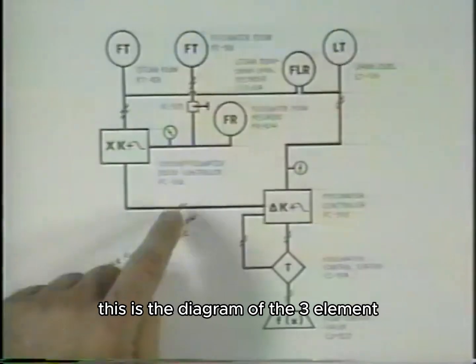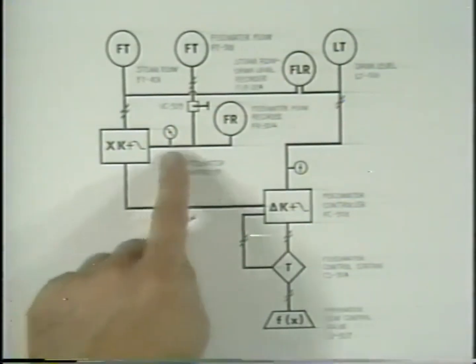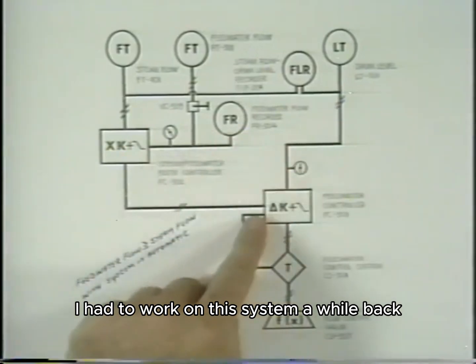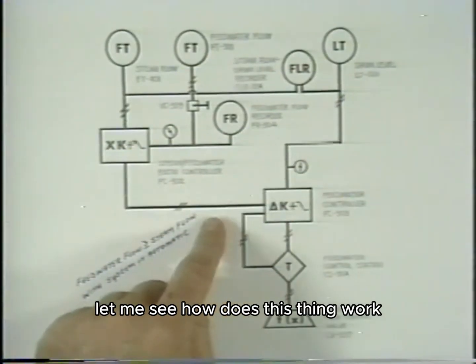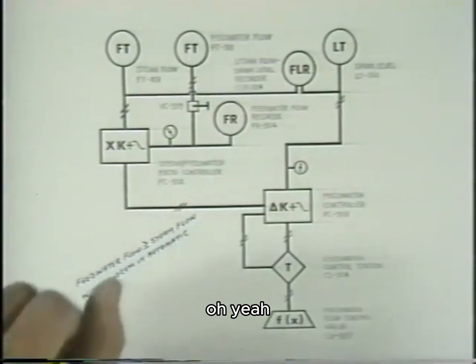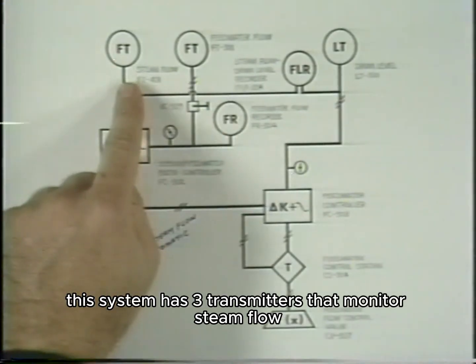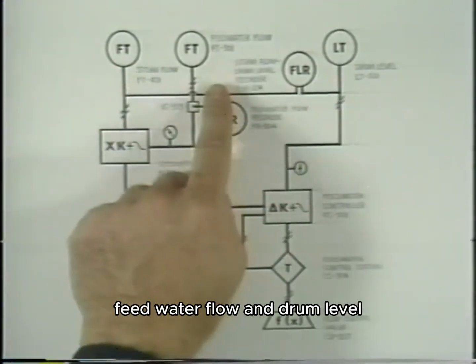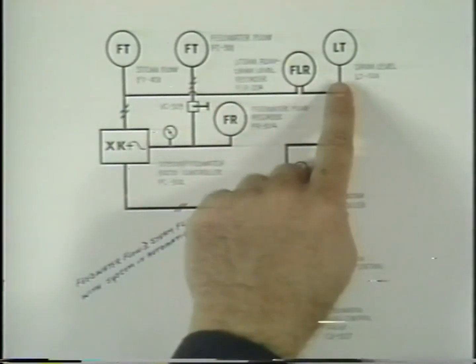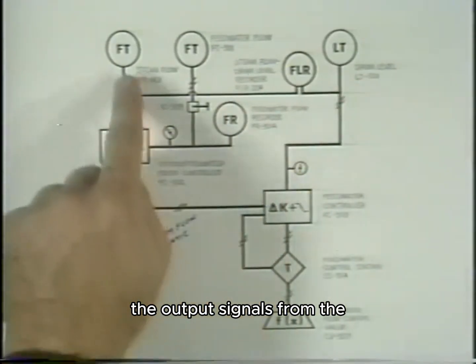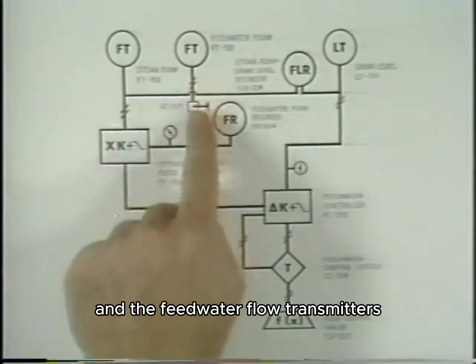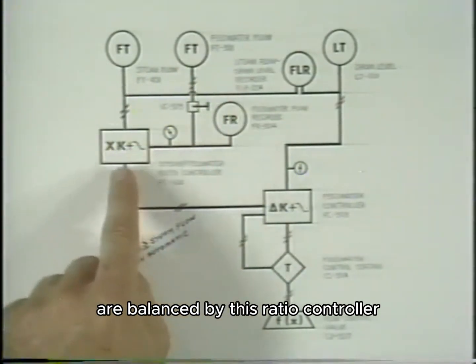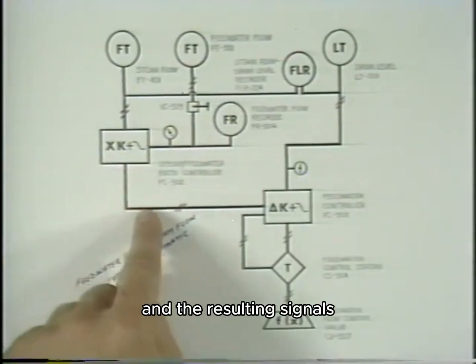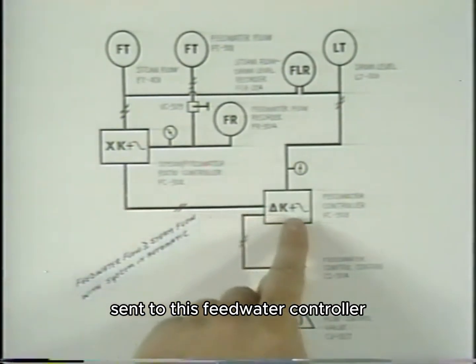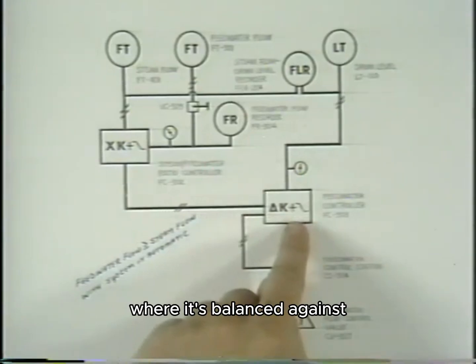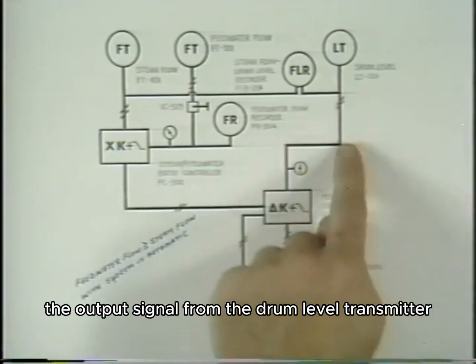This is the diagram of the three-element feed water control system. I had to work on this system a while back. Let me see. How does this thing work? Oh yeah. This system has three transmitters that monitor steam flow, feed water flow, and drum level. The output signals from the steam flow transmitter and the feed water flow transmitters are balanced by this ratio controller, and the resulting signals sent to this feed water controller, where it's balanced against the output signal from the drum level transmitter.